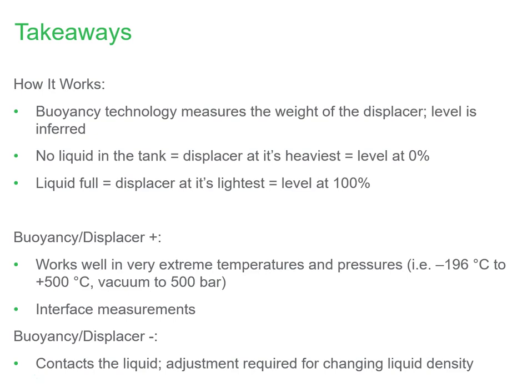The benefits of buoyancy are that it's very good for high temperatures and pressures. It's easier to make an interface measurement with buoyancy than it is with some instruments like guided wave radar. With buoyancy, you don't need two separate individual levels or rag layers to measure interface. And this technology has been around since Archimedes' time, so it's a proven method of measuring liquid level.